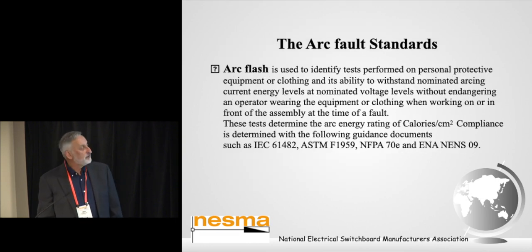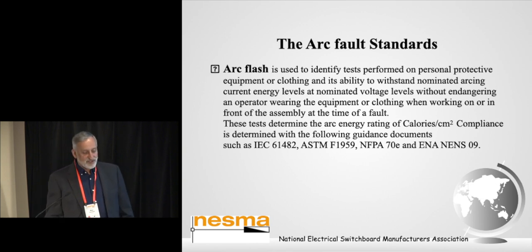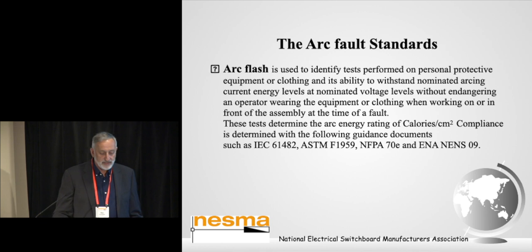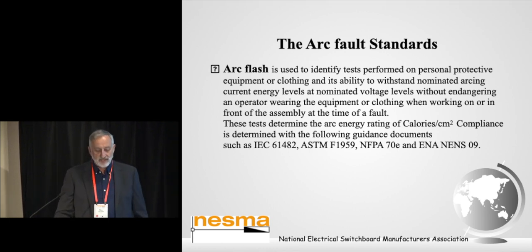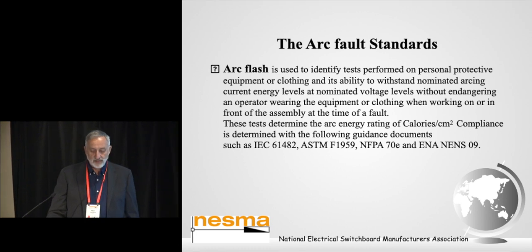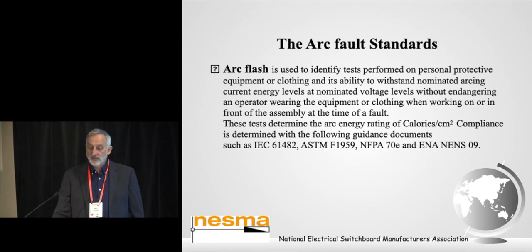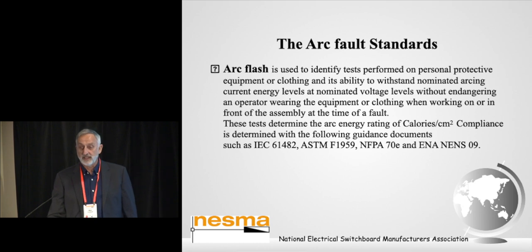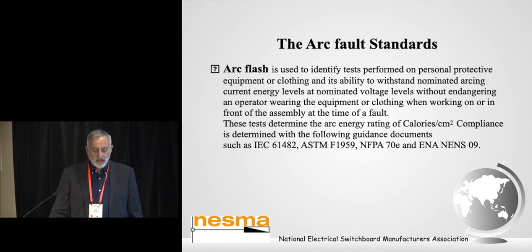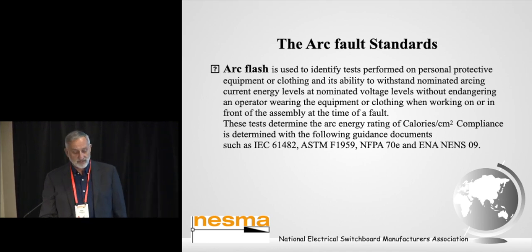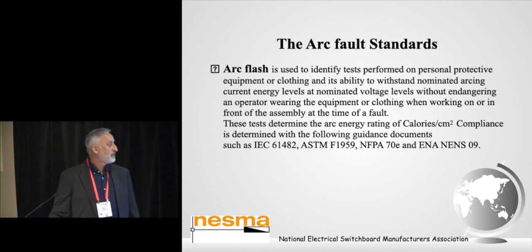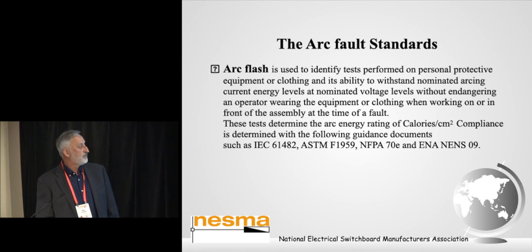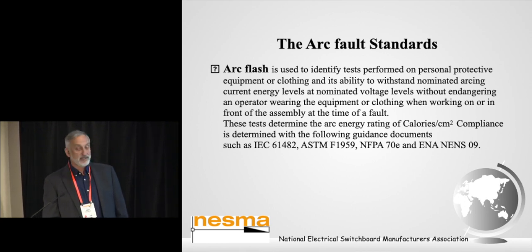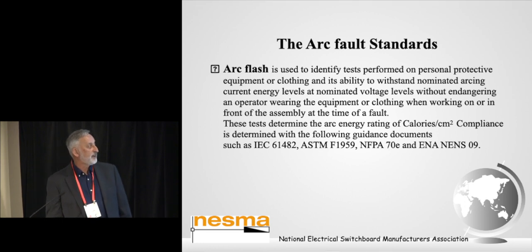So the arc flash that I mentioned earlier is used to identify tests performed on personal protective equipment or clothing, and its ability to withstand a nominated arcing current energy levels at nominated voltage levels. So without endangering an operator wearing the equipment or clothing when working on, in, or in front of an assembly at the time of the fault. So these tests determine the arc energy rating or calories per centimetre squared, and compliance is determined with the following guidance documents. So IEC 61482, the ASTM F1959, NFPA 70E, which is a number you might see, and the ENA NENS 09.